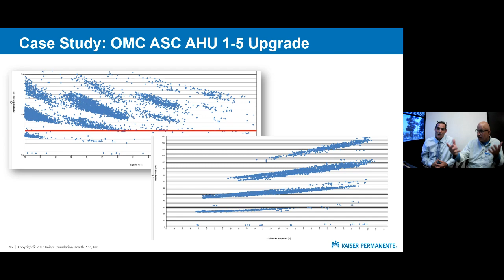Yeah. So we did revise the acceptance criteria. As you can see, chiller turn down was removed because they were running 24/7. The kW per ton was revised to 1.82, and so that passed. AHU night setback, the temperature setbacks, the commissioning agent did functionally test them and make sure that worked, but it was locked out, so nothing was implemented. And so we can see still opportunities missed. We're still hitting the nail on the head here: fan power and turn down at the zone level.